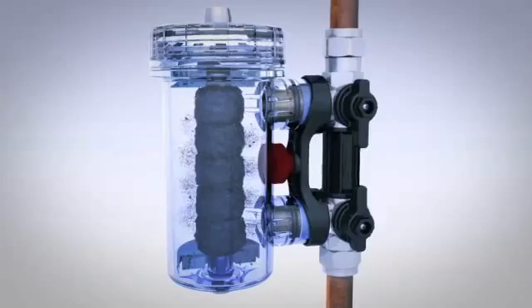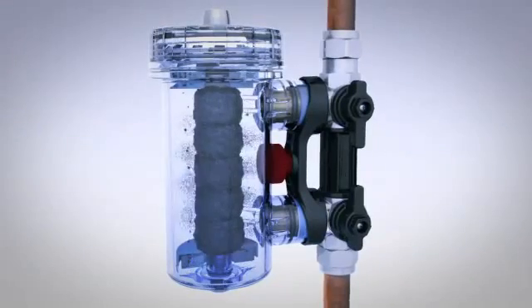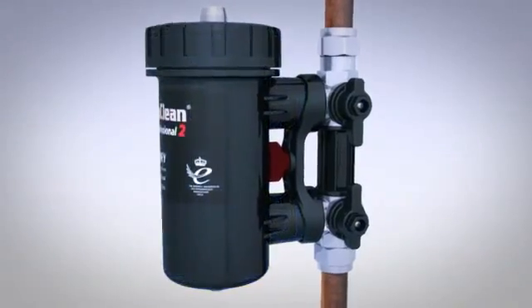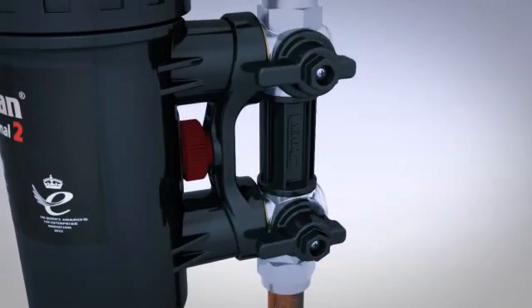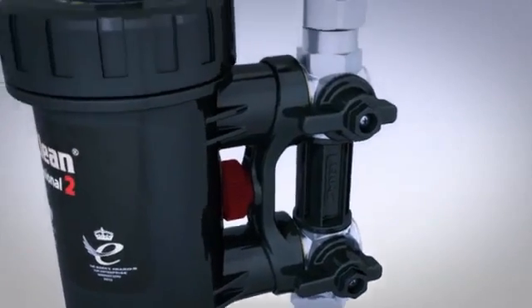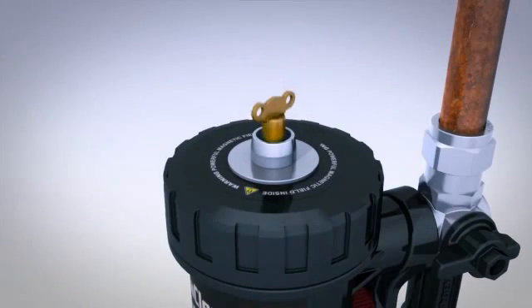All MagnaClean filters allow full flow at all times, even when fully saturated. To service the filter, first turn off both isolation valves, then loosen the air vent to release any internal pressure.